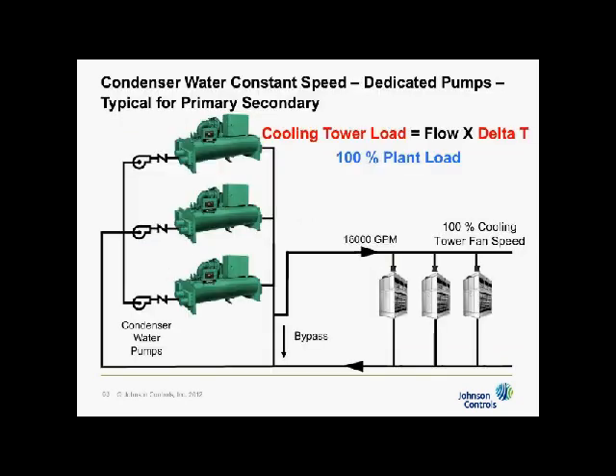First, we're going to look at a typical condenser water system: constant speed, dedicated pumps, that you would normally see with a primary-secondary plant, and we still have the same rules as before. Cooling tower load is flow times delta T. Here's a typical diagram. We have the condenser water pumps, dedicated per chiller. We have cooling towers. We have a typical 16,000 GPM total for 100% plant load.